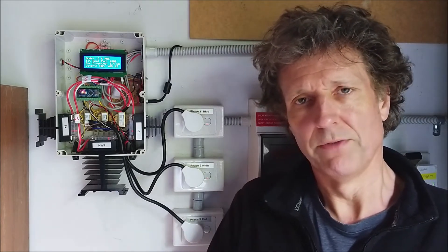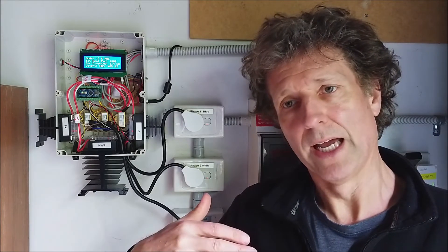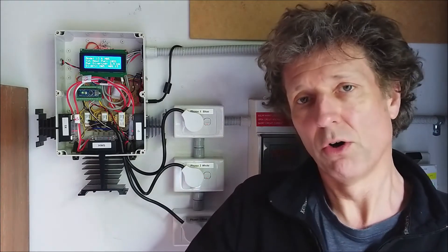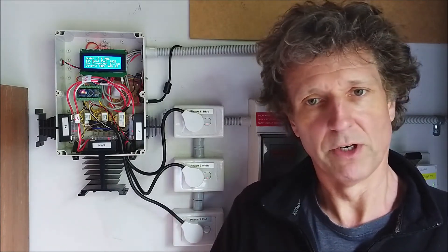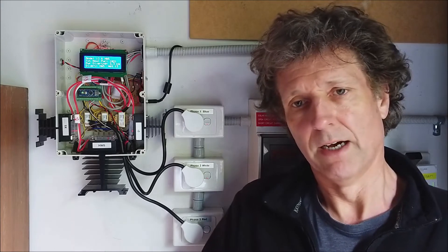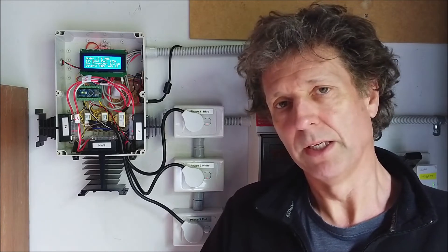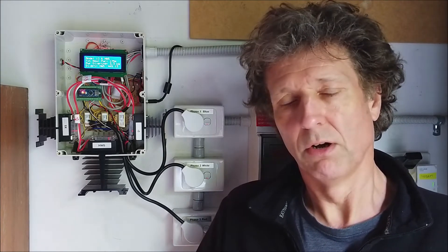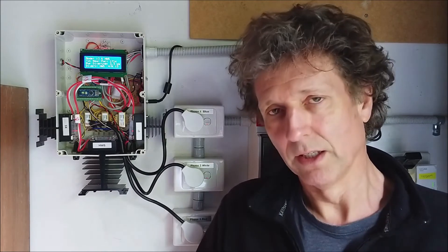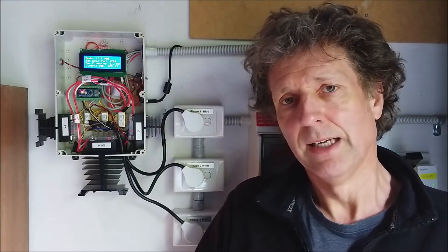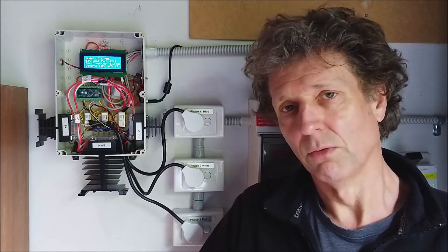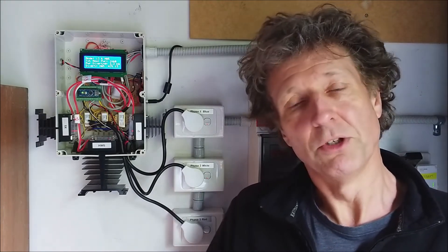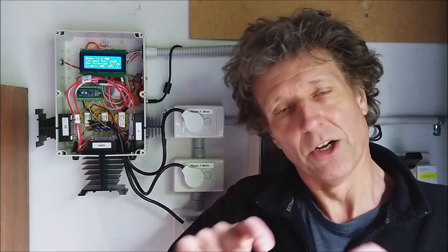You recall that with the previous system I really only had the system on or off based on a specific threshold. Now an example might be, on an overcast day we're exporting 1 kilowatt to the grid and I switch on my hot water service of 1.8 kilowatts. I'd still be draining 800 watts from the grid but at least I'd be getting the 1 kilowatt advantage and I could hopefully spread that over the course of the day.